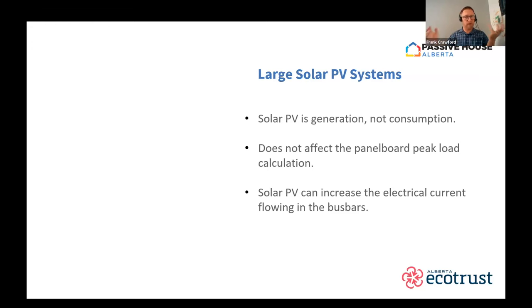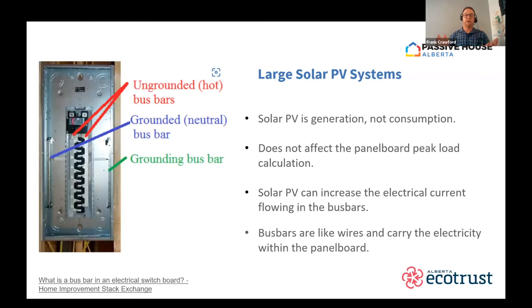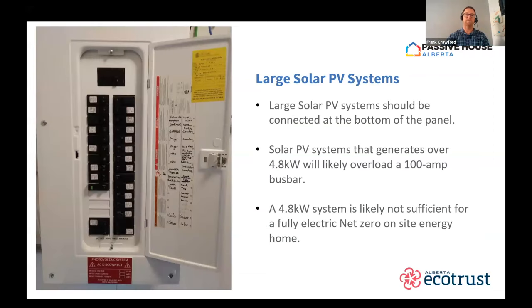So your next question is, what's a bus bar? I had that same question. Basically, the bus bars are kind of like the wires, and they carry the electricity within your electrical panel from the wires that come from the transmission to each individual breaker. And there's a whole bunch of electrical code calculations on how much electricity can be flowing through those bus bars. So generally speaking, that solar PV system wants to be connected at the bottom of the panel. So its generation comes from the bottom and your grid electricity comes from the top. And hopefully, and theoretically, they never meet. But again, there's a whole bunch of code clauses to make sure that that is a safe connection.